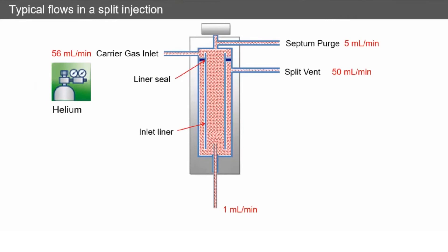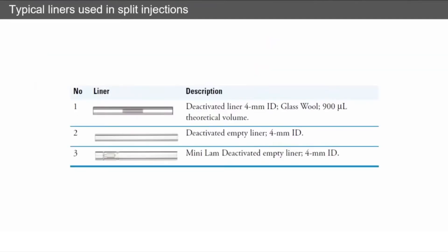And then we've got only 1 milliliter per minute going down our column, which is a tiny percentage of the total flow. All of the flow within the column is controlled by the pressure in the injector. There is no flow restrictors or anything after the inlet, and that's how we control it.